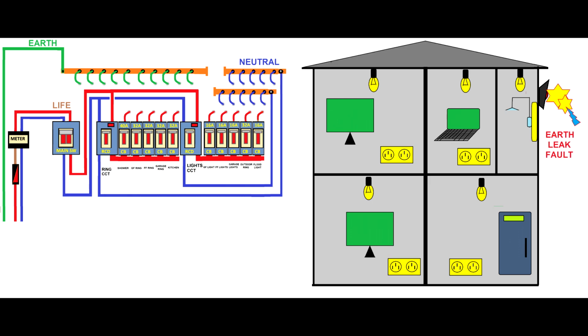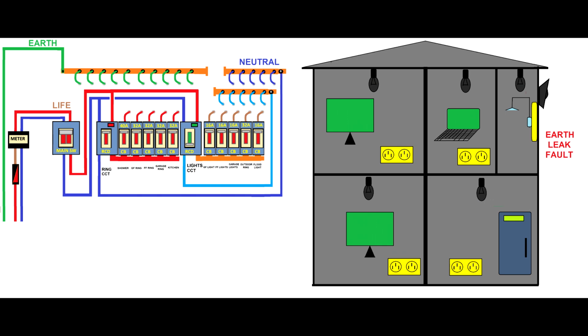You just turn on the last circuit breaker and you realize that your residual current device just tripped. Now you lost the light, so you understood that if you activate the last circuit breaker, which is the floodlight, your RCD is tripping.